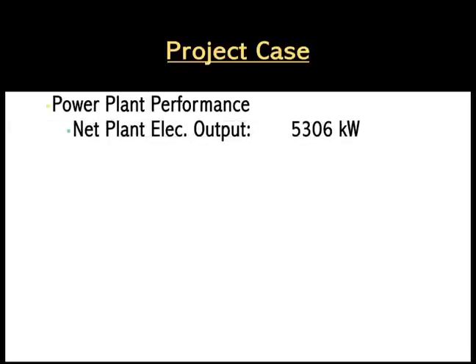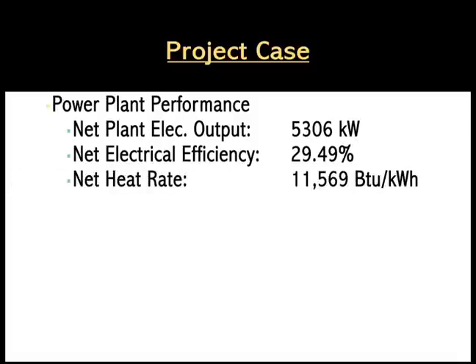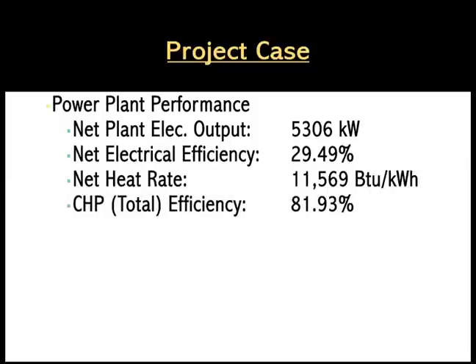A net electric output of 5,306 kilowatts, a net electrical efficiency just under 30 percent, the net heat rate was 11,569 BTU per kilowatt hour, and a CHP total combined heat and power efficiency just under 82 percent.